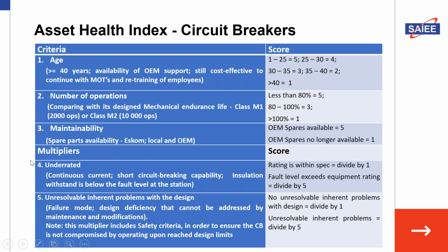If it's underrated where it's been deployed, then we have a problem, and we amplify that situation, and we say look, regardless of how healthy it may have been at the top, it's in the wrong place, because it will not withstand full faults if they should happen, as an example, because the kiloamp rating of the site is much, much higher. The breaker will simply explode and be obliterated.